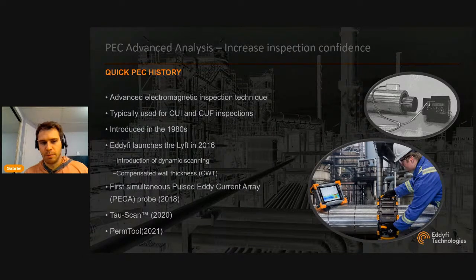The technology was used pretty much similarly from the 80s till the mid-2010s. And then Eddyfi launched in 2016 the Lyft, our own implementation of pulse eddy current. This was the first PEC system on the market with dynamic scanning, which means that instead of a grid mode where you take point-by-point measurements, we are able to use an encoder to trigger the acquisition cycle and just scan at a nearly constant speed on the surface, which dramatically increased productivity. We also introduced the compensated wall thickness, a tool that will extract the contribution from a defect to minimize the undersizing effect of small flaws. It is intrinsic to pulse eddy current.